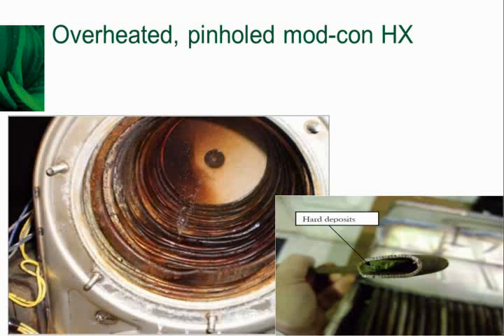And so now when the flame came on inside this heat exchanger, it wasn't getting the heat to the water. It was actually becoming an insulator on that tube, and you can see by the color of the tubes where the burner was going in that it was overheating, and it finally fatigued the metal to the point where it developed a pinhole. So two things to be said on this. Obviously, this was a closed-loop hydronic system. We're not looking at a potable water system, and it was a case of taking on water constantly. It had a leak in the system somewhere, as I recall, and it was taking on water, plugging up the heat exchanger, or at least coating the heat exchanger so that you didn't get the heat transfer to the water, and then stressing the metal.